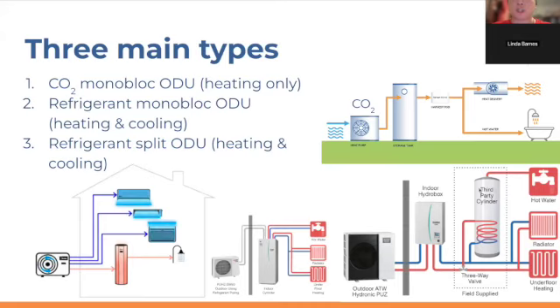So in terms of examples of these systems, the upper right-hand figure shows a CO2 monoblock system. The lower right-hand corner shows a refrigerant monoblock system. So a system that pipes water with some percent glycol mixed in it, and then the outdoor unit has your refrigerant contained only in that outdoor unit, and the outdoor unit has a heat exchanger that takes the heat from the refrigerant and transfers it to that water or water glycol mixture, so that the intermediary working fluid is the water or water glycol fluid that goes inside the home.